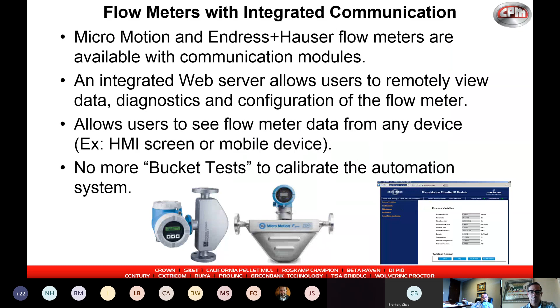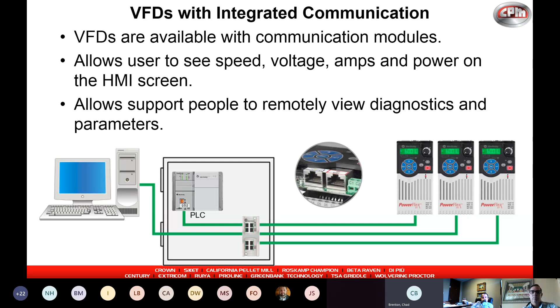The same goes for VFDs. Before, we used to just send start, stop, and a speed command. Now we can get back from those VFDs the amps, the power consumption, and any fault codes, so we know exactly what went wrong before a maintenance person has to go out to the VFD itself and read a fault off of it. We can display all that on the system.